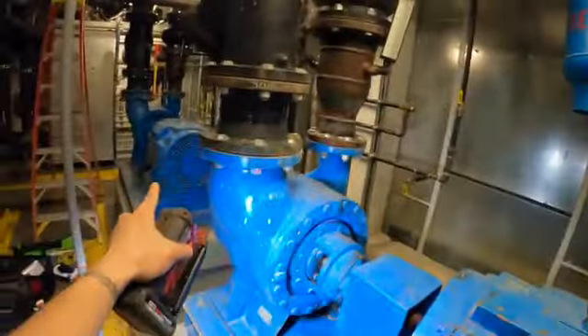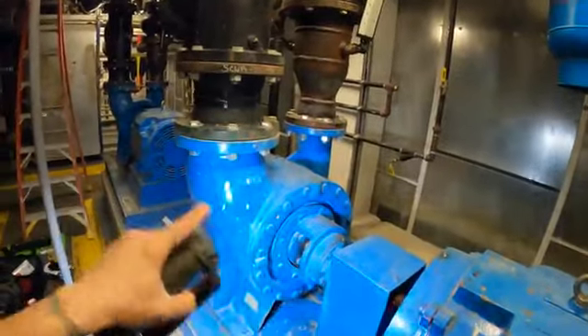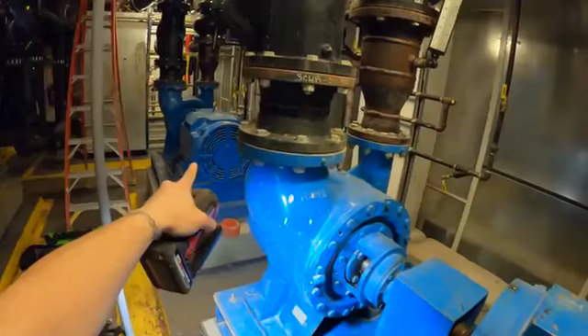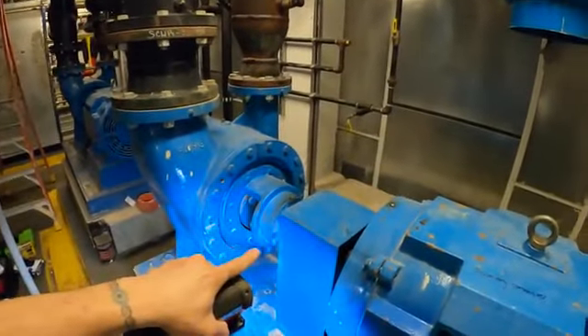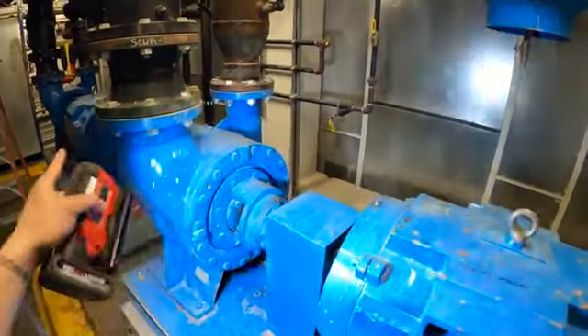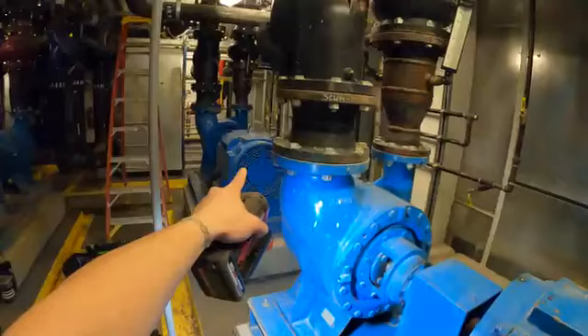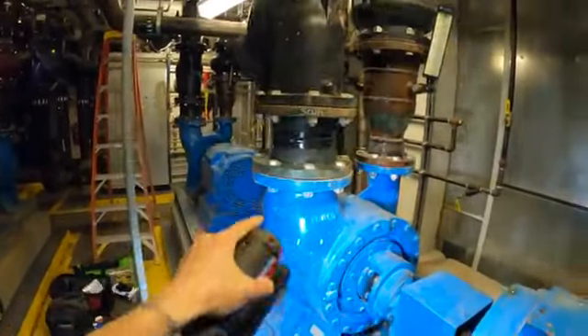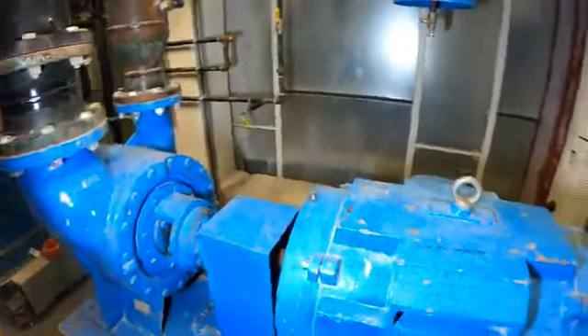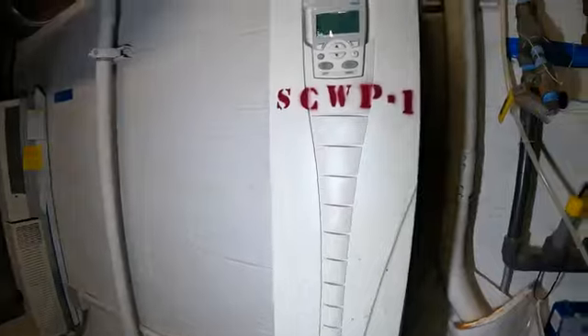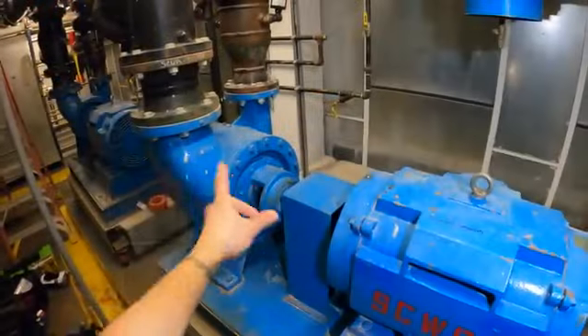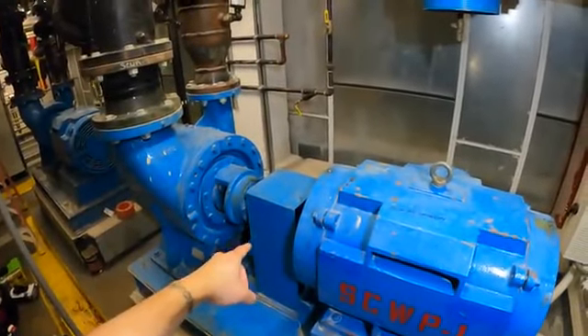You want these in auto, so these pumps can auto rotate. This one might run for a certain amount of hours, then this one will come on and run for a certain amount of hours, and they switch off. But this thing's been running non-stop for thousands and thousands of hours, so they gotta get their BMS guys over here. So we're probably just gonna have to turn this thing on hand and turn that off. Before we shut that down, we want this one to run, because they need to run all the time.